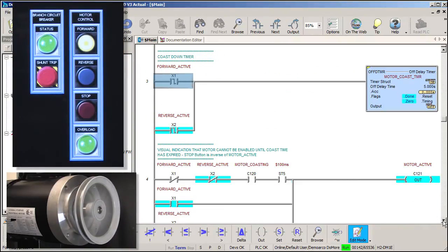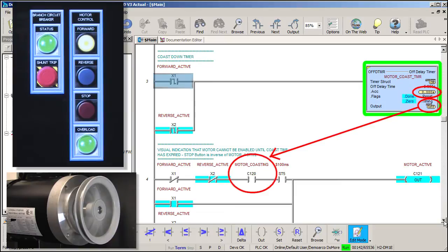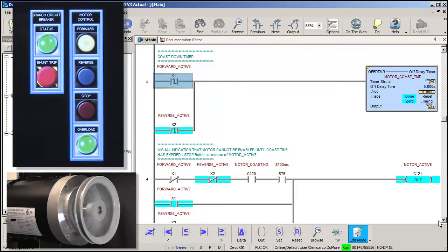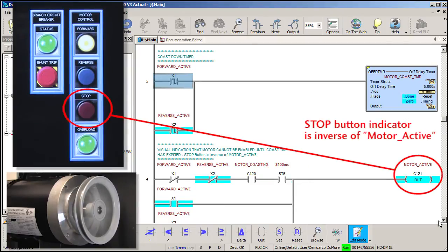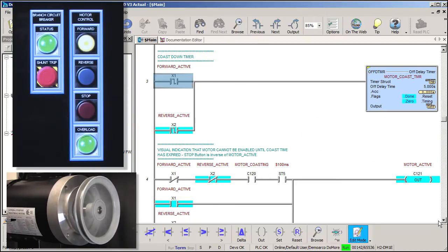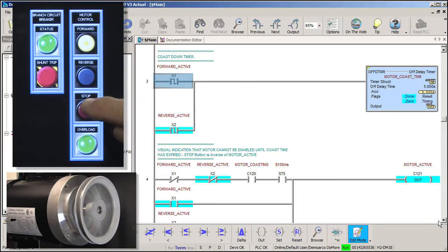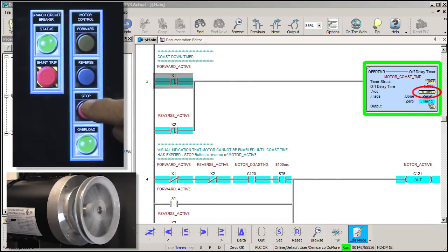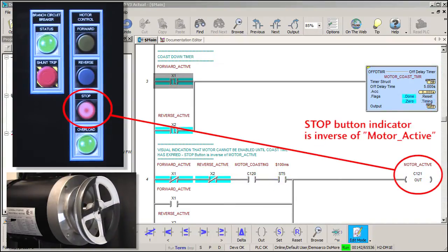This time, when we press the stop button, we should see this off delay timer countdown for 5 seconds, which will turn this motor coasting bit on and its aux contact will go inactive, which will light up this contact. Then every time the system 100 millisecond bit is active, the motor active bit will turn on. The stop button indicator light is just the inverse of this motor active bit, so if the motor is not active, the stop button will be lit. Of course, if either contactor is inactive, then the motor will also be inactive, which again will light the stop indicator. Let's try it – when we press the stop button, the timer counts down, the motor coasting bit goes active, the aux contact releases and sure enough, the stop button indicator flashes. Perfect.